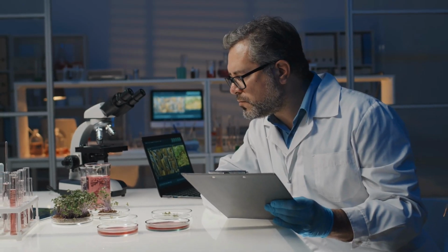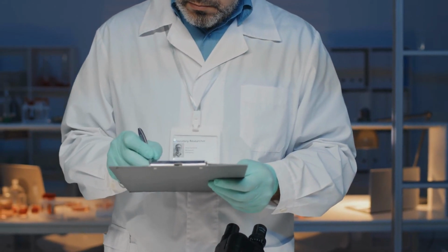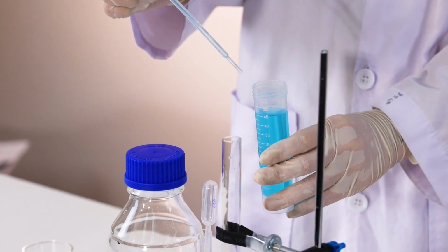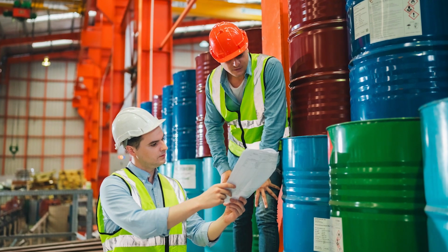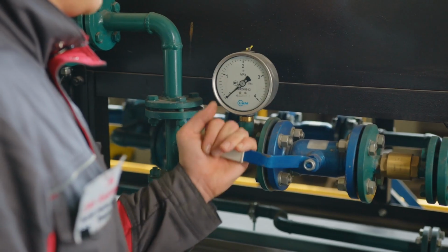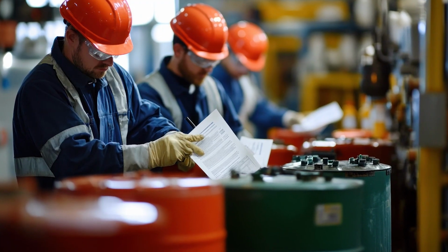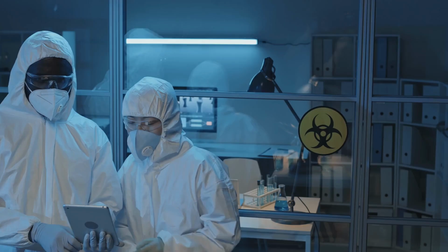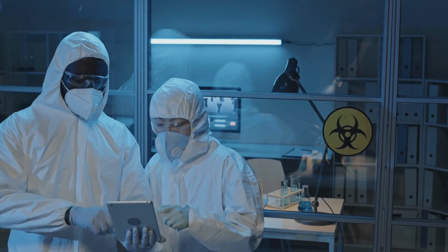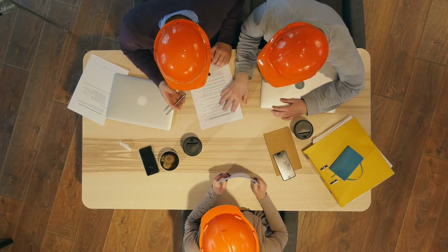Information on the technology of the process must include a block flow diagram or simplified process flow diagram, process chemistry, maximum intended inventory, safe upper and lower limits for temperatures, pressures, flows or compositions, and an evaluation of the consequences of deviations, including those affecting the safety and health of employees. OSHA provides options when this information is no longer available.